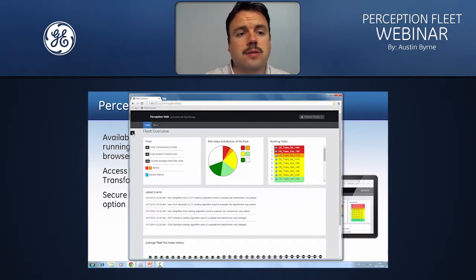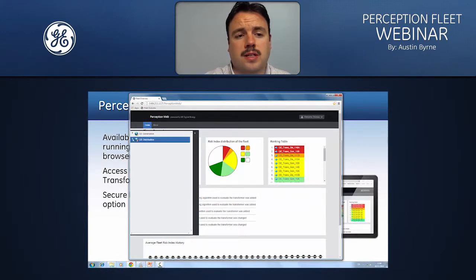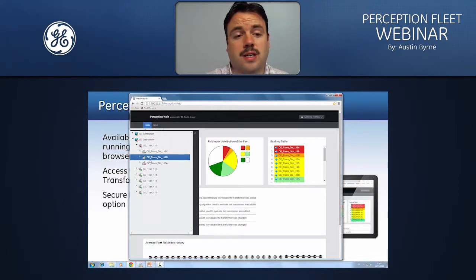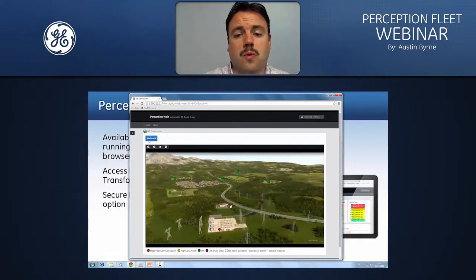I can also click on this arrow here and it will show me the asset tree. If I drop down, you can see these are all the substations and then the subsequent transformers under the substations within my particular Perception Fleet asset hierarchy. If I click on this GE distribution area, it'll pop open the wallboard that I have configured for the Perception Fleet application. So you can see the wallboard is a virtual representation of your asset fleet. You can apply any image as your wallboard image, whether it's an aerial screenshot or an image that's taken from an online map service.